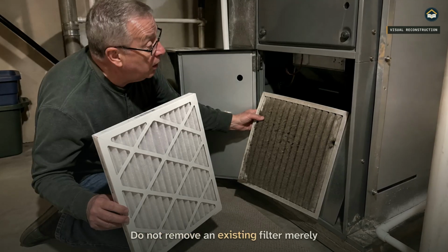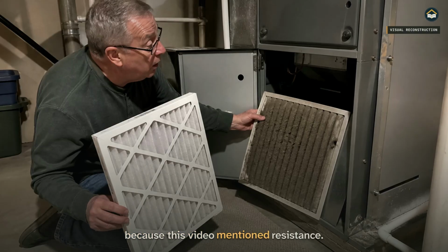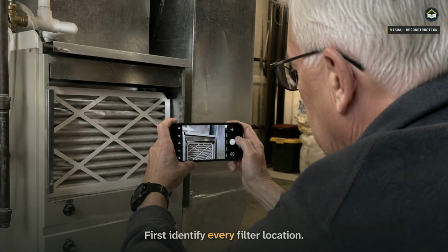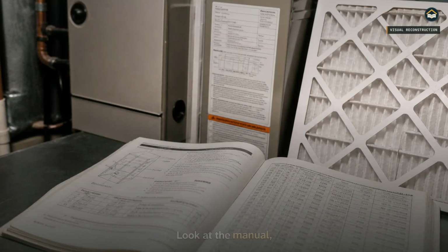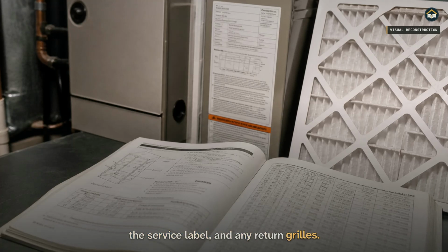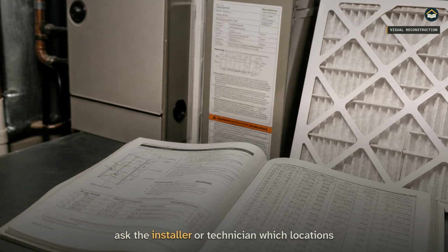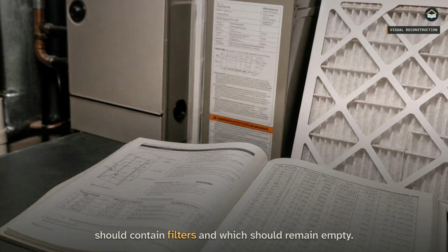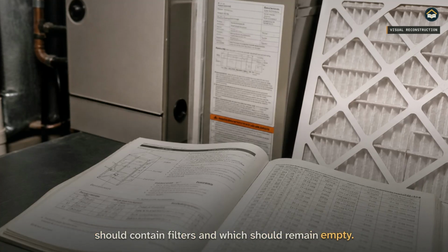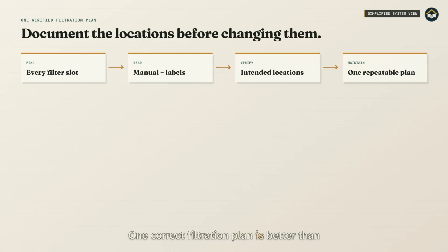Do not remove an existing filter merely because this video mentioned resistance. First, identify every filter location. Look at the manual, the service label, and any return grills. If the arrangement is unclear, ask the installer or technician which locations should contain filters and which should remain empty. One correct filtration plan is better than 2 filters installed by assumption.